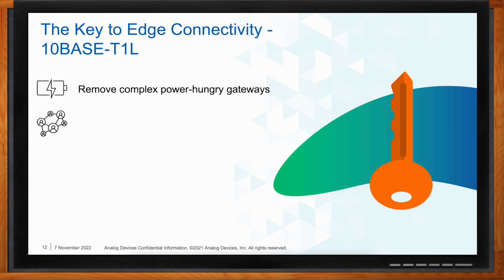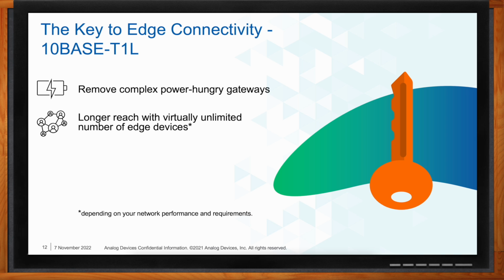The second takeaway is that by using 10BASE-T1L building controllers, we are able to achieve longer reach with virtually an unlimited number of edge devices, depending on your network performance and requirements. The last takeaway is that 10BASE-T1L enabled building controllers are able to monitor your network failures and identify cable issues in real time using fault detection and cable diagnostic features.